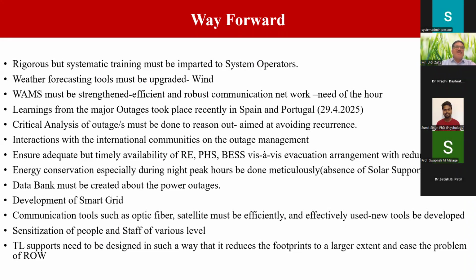For that, the WAMS area, that is the wide area monitoring system, must be strengthened, which determines reactive power flow, active power flow, and voltage dips, leading to collapse of the grid. This WAMS, also called phasor measurement units, needs to be installed at every critical point, and its data needs to be meticulously analyzed so that grid parameters don't go out of control.